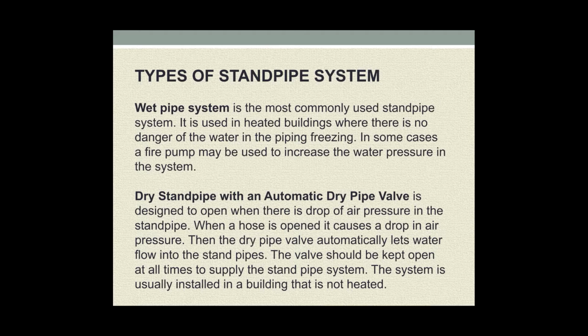Next, dry standpipe with an automatic dry pipe valve. It's designed to open when there is a drop of air pressure in the standpipe. When a hose is open, it causes a drop in air pressure. Then the dry pipe valve automatically lets water flow into the standpipes. The valve should be kept open at all times to supply the standpipe system. The system is usually installed in a building that is not heated.